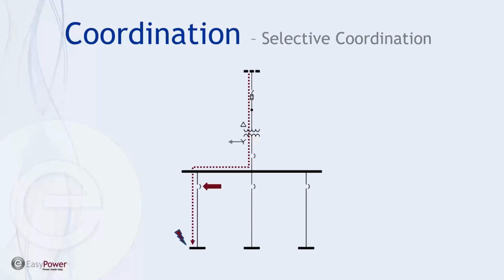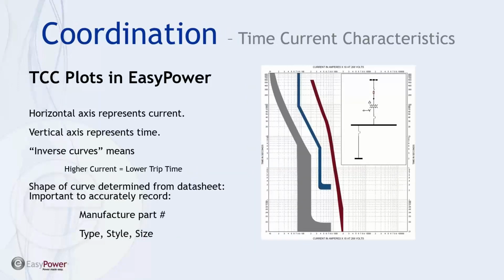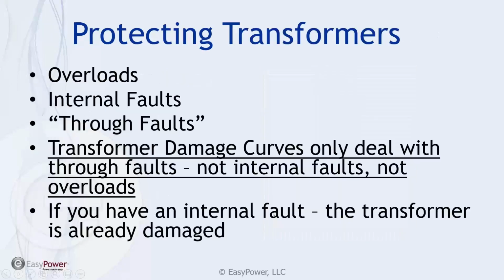Now, the most important tool, or the most utilizable tool for this process, is what we call time current characteristic plots. And they have been in use for as long as there have been protective devices. For those that haven't used them much, they present a little bit of a dilemma because they're somewhat different from what we're used to. We're used to having charts or graphs where we have time along the horizontal axis. In a time current characteristic plot, time is in the vertical axis and amperes, or current, is in the horizontal axis. Most of the elements that we're going to be looking at are considered to be inverse reactions, which means the higher the current, the faster the device will respond.